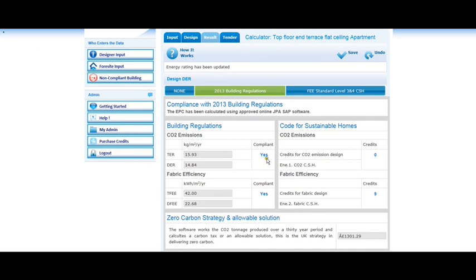We have an even better compliance with DFEE, and we've just about achieved DER compliance. In some cases, even with the additional insulation and added cost of passive windows, DER compliance is not attainable. If this is the case, a decision needs to be made by the designer. Do they add the extra cost of insulation and windows to the build costs and still be non-compliant, or stick with the FEE design? From our experience, the FEE standard is as high a performance that can be achieved with apartments with the technology that is in common use at the moment.